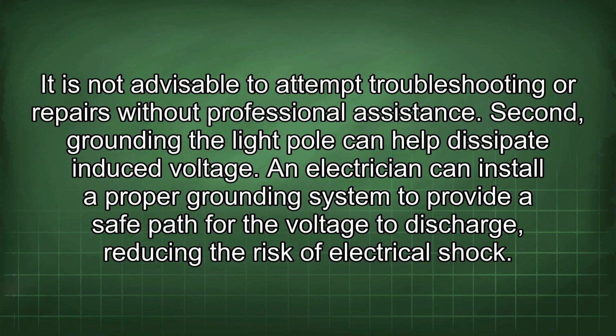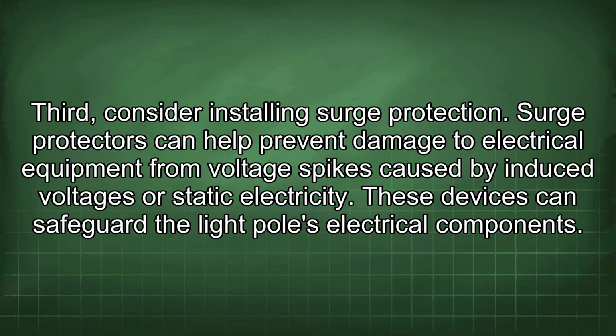Second, grounding the light pole can help dissipate induced voltage. An electrician can install a proper grounding system to provide a safe path for the voltage to discharge, reducing the risk of electrical shock. Third, consider installing surge protection. Surge protectors can help prevent damage to electrical equipment from voltage spikes caused by induced voltages or static electricity. These devices can safeguard the light pole's electrical components.